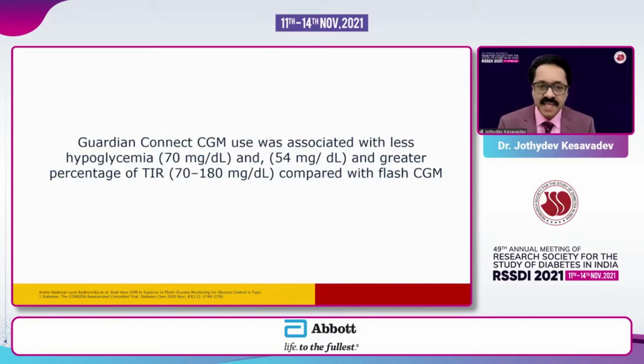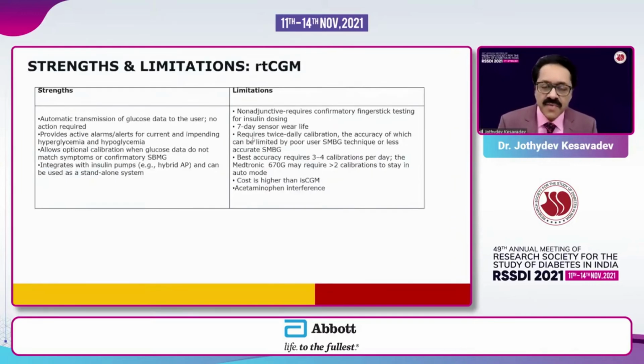The real-time device is associated with less hypoglycemia, both level 1 and level 2, that is below 70 and below 54. And there is a significantly higher percentage of time between 70 and 180 when you are making use of real-time CGM devices. Each one of those will have its own strengths and limitations. The strength with the real-time is the data, which is continuously available with no action required. And it even allows calibration with a glucose meter. The limitations: you require a glucose meter for calibration, the sensor life is only 7 days, the cost is very high, and paracetamol interference is also a concern.